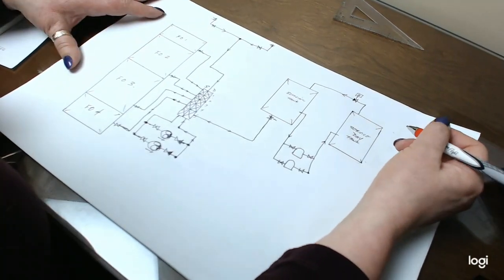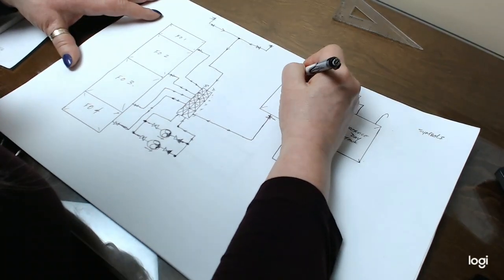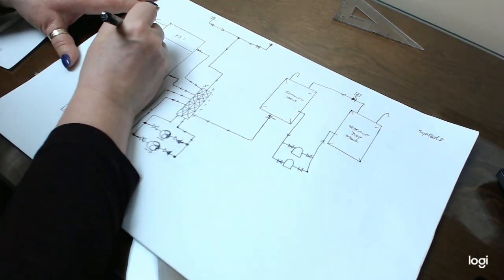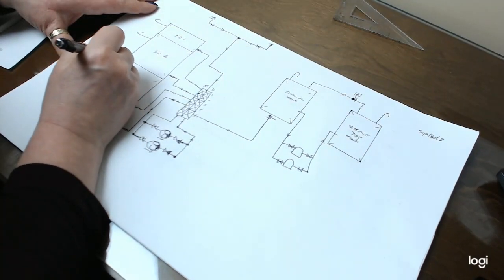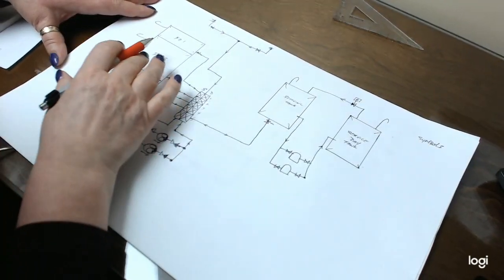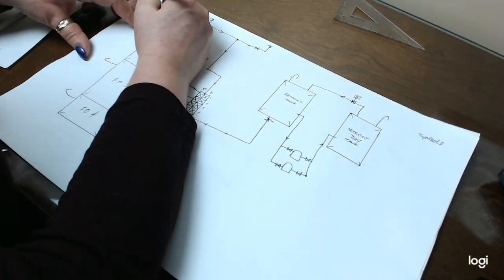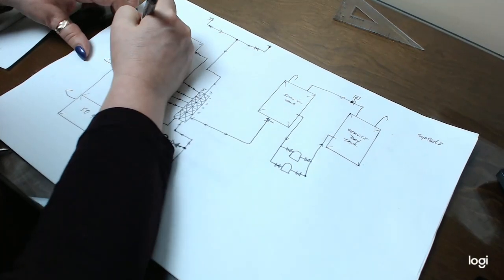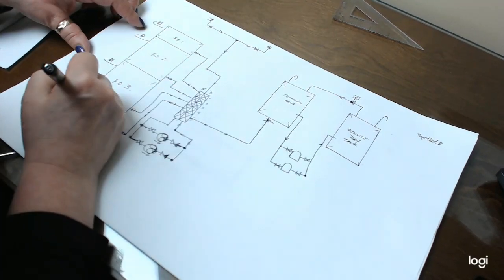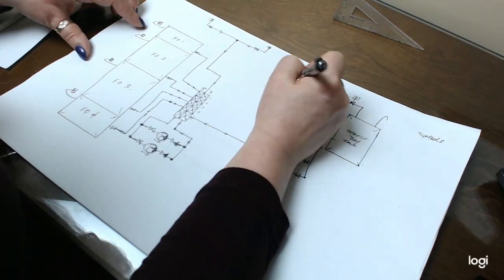Another piece that you want to look at is the fact that all of these tanks would have vents. Okay, so I'm just going to draw these lines as vents, and I'm going to put this out here. Sometimes, when you're looking at the rules for design, the vents are normally called air pipes as well. They are put in, and they're just looking like that. These pipes would eventually have pieces on them, like a ball set up, so water can't get back into it. So you can show your fuel pipe vents like this, or your fuel tank vents like that.